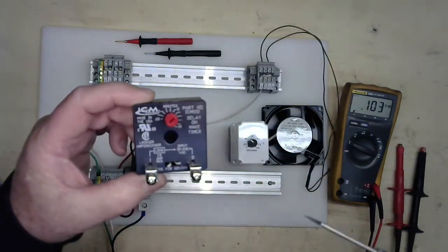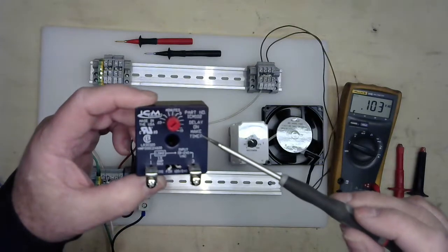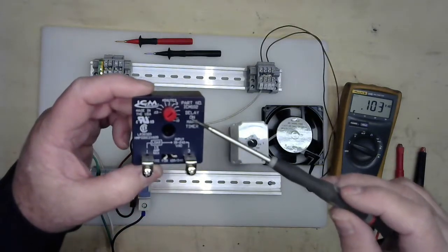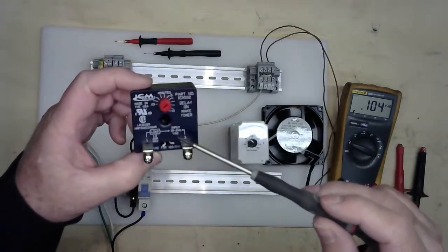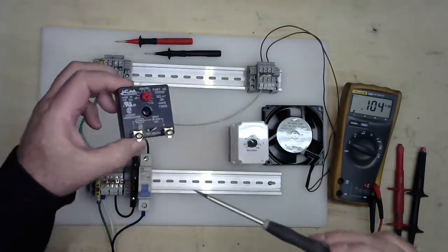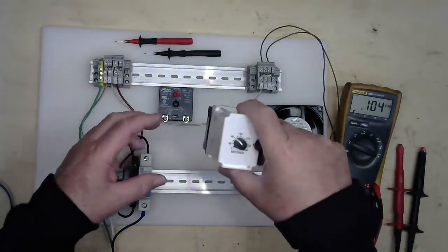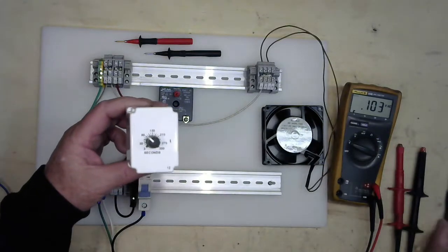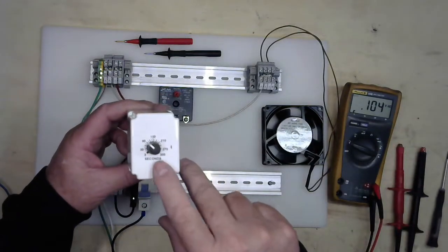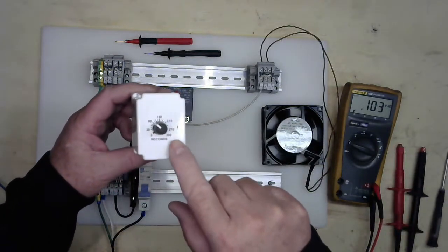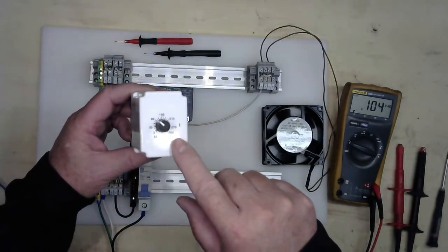These are typically used in various applications. HVAC is the most common. They can be used in any kind of application where you want to have just a single input to one output. This particular type of time delay relay is adjustable from 3 seconds to 300 seconds. They do make them in minutes and possibly hours.